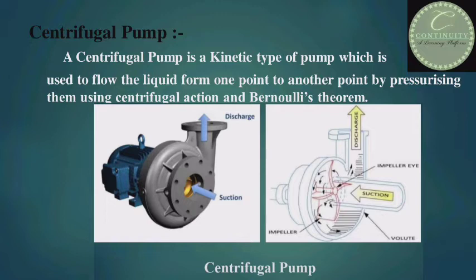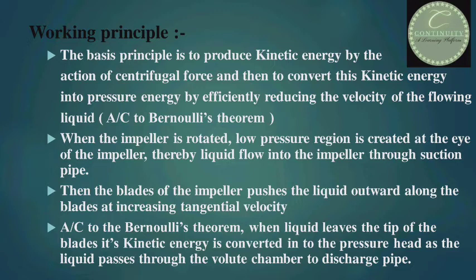Now we will discuss the working principle of the centrifugal pump — how it works. The basic working principle is to produce kinetic energy by the action of centrifugal force, and then to convert this kinetic energy into pressure energy by reducing the velocity of the flowing liquid, according to Bernoulli's theorem. When the impeller is rotated, a low pressure region is created at the eye of the impeller.